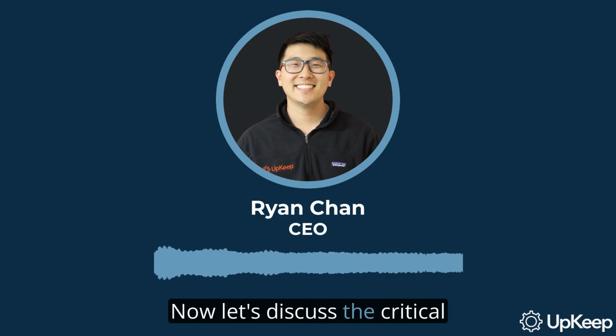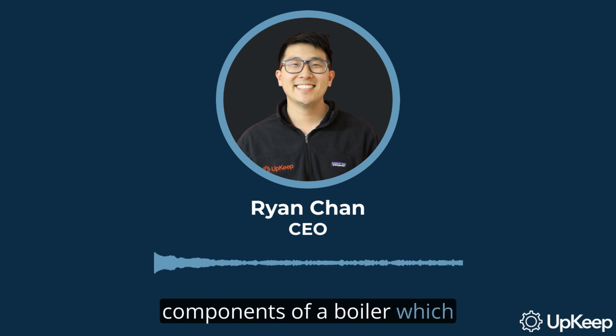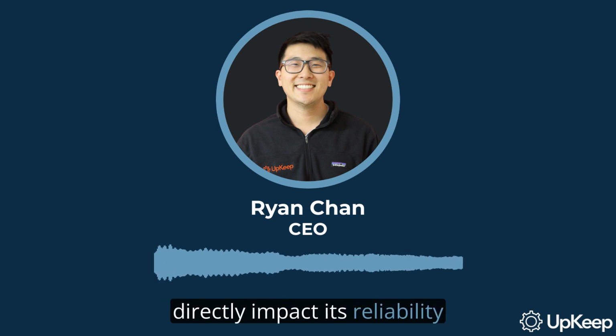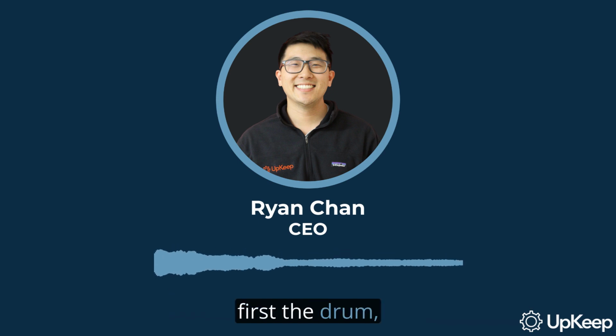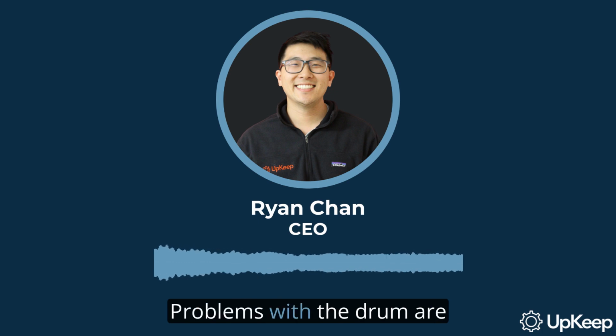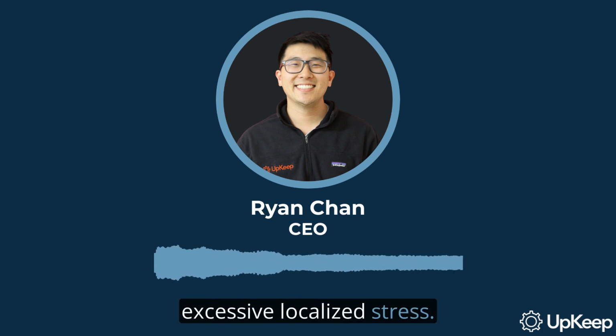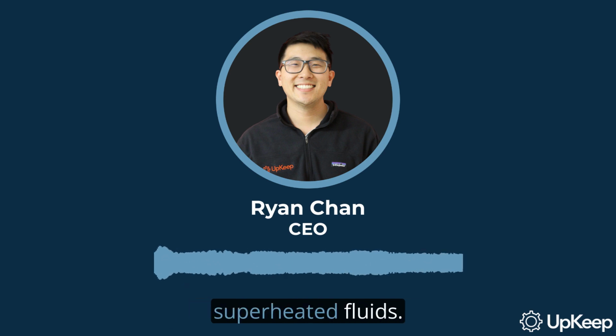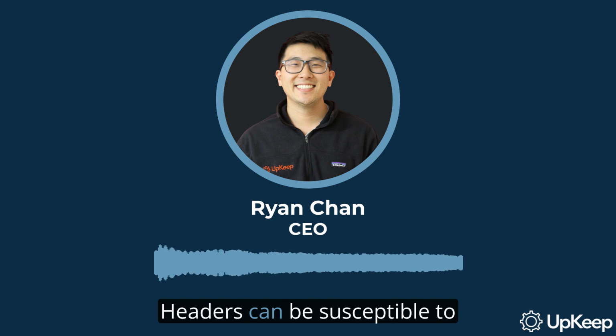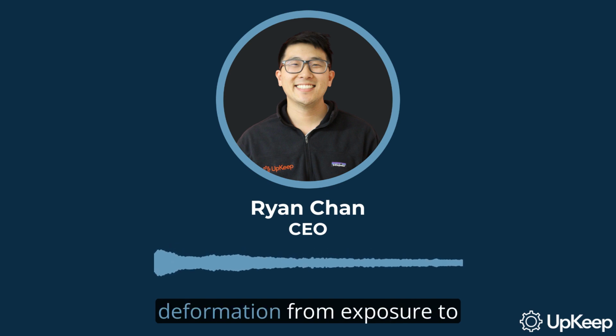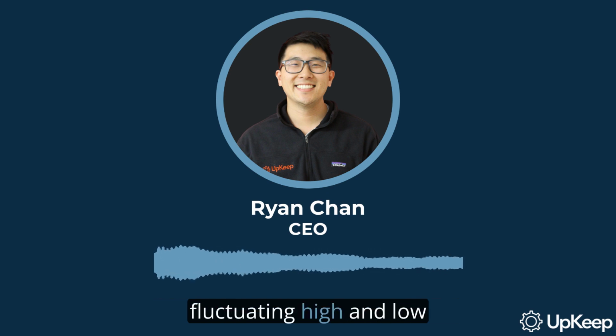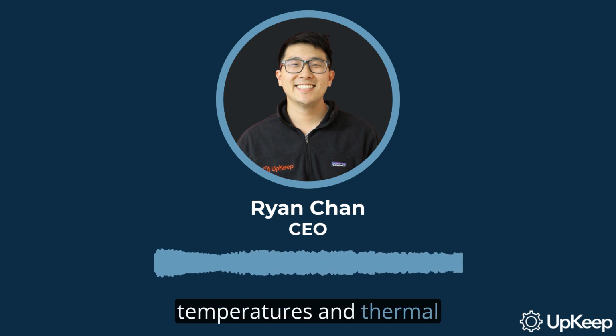Now, let's discuss the critical components of a boiler, which directly impact its reliability and safety. These components include, first, the drum, which is the single most expensive part of the boiler. Problems with the drum are usually related to corrosion or excessive localized stress. Next, we have headers, which act as outlets for superheated fluids. Headers can be susceptible to deformation from exposure to fluctuating high and low temperatures and thermal stresses.